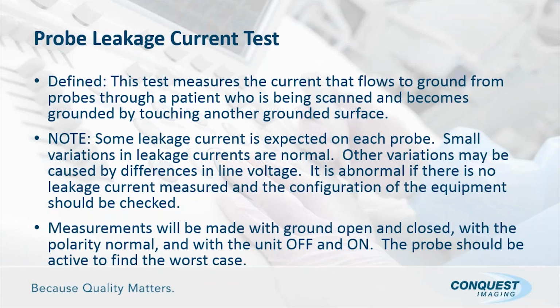That's kind of a weird statement in effect. The reason I say it's unusual is because I've run across probes where there is no leakage current that is measurable. So I like to point that out, because if you're doing an electrical safety test on a probe and you get 0, there's probably some amount of leakage. It's just so small you can't measure it using the meter we have. But in reality, it's normal around, my analyzer will read 001, and so my leakage is 1 microamp, and clearly that's tolerable. So if you get 0 leakage on some probes, you're probably okay.